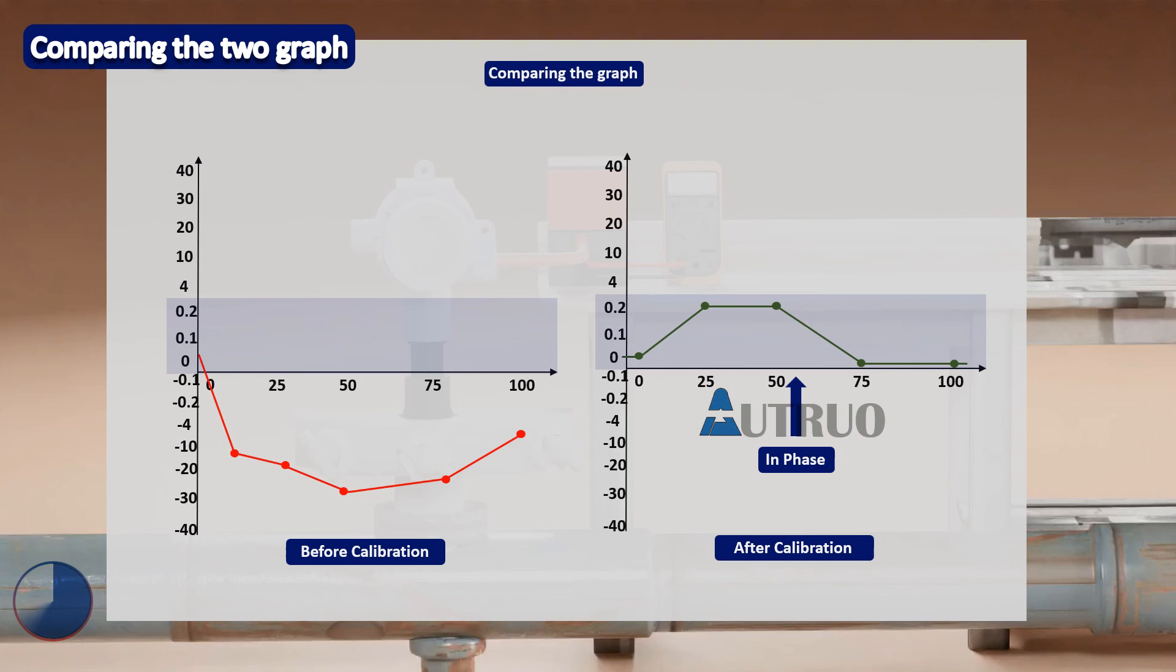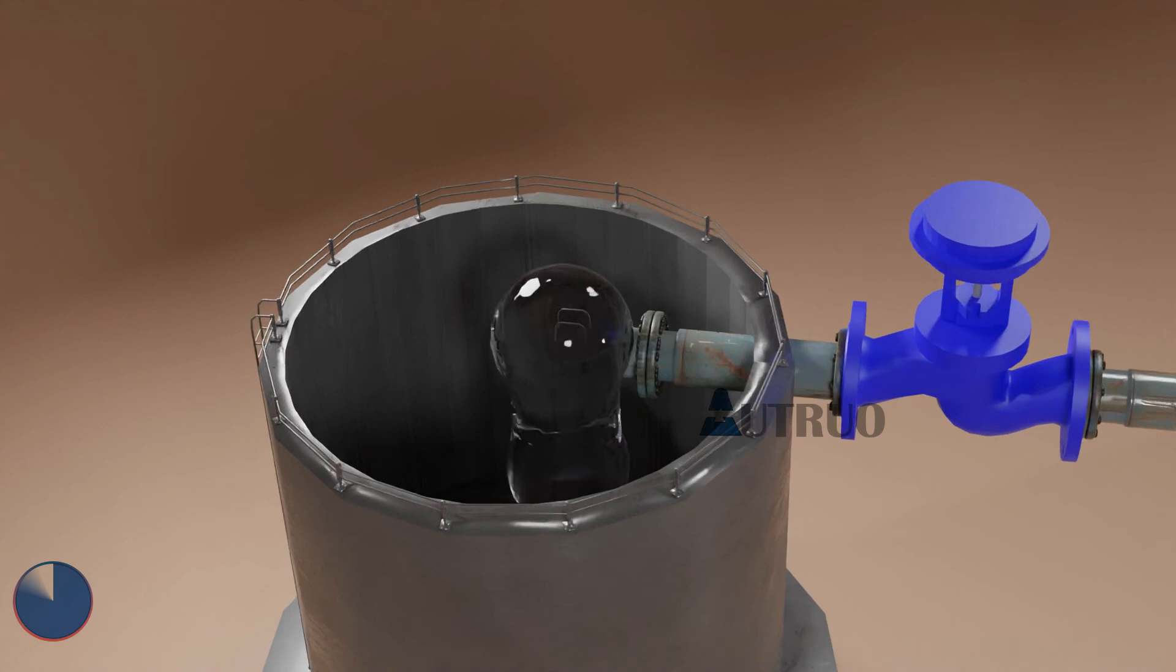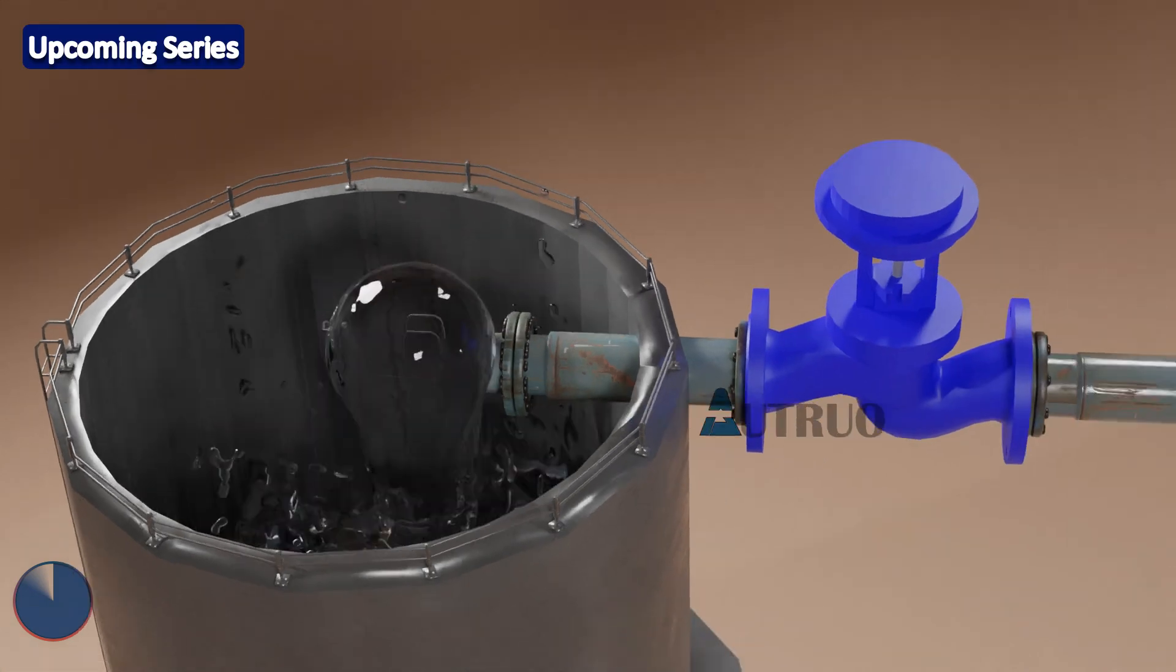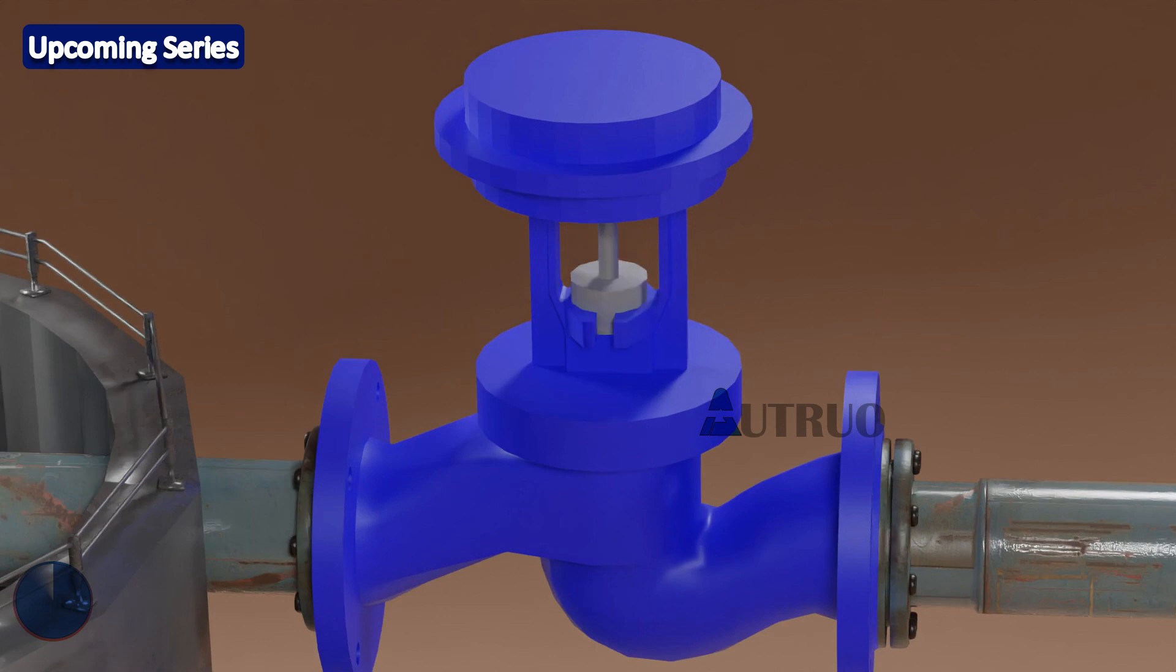Now what we just did is known as transmitter trimming. What we did was to trim off the transmitter in such a way that the current signal will be equivalent to the fluid flowing within a pipe. Hence, a well functioning transmitter will improve the quality of the products produced, because the current going to the PLC will represent reality. That is, when we allow 10 gallons of water to flow within a pipe, we will be getting 10 gallons at the output of the tank before the PLC closes the inlet valves of the process equipment.